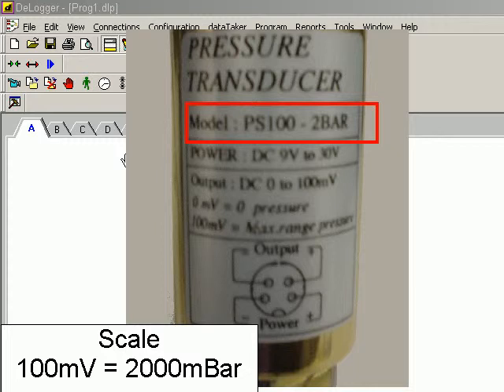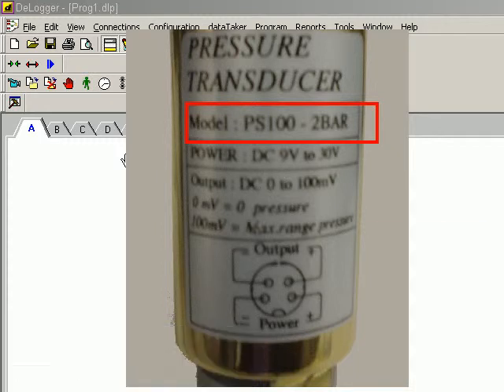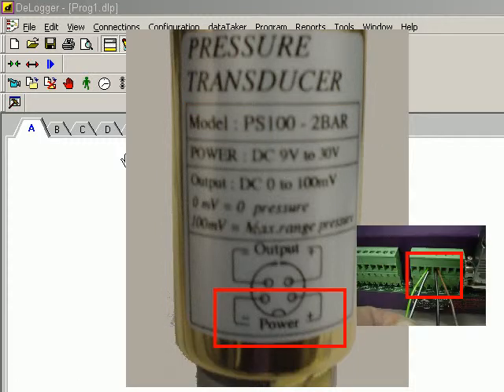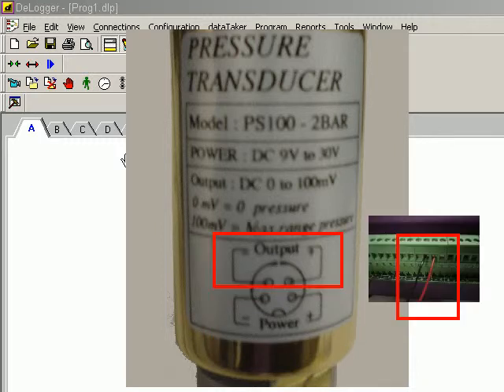The power plus and minus are connected to the power supply plus and minus. You need to double-check to ensure you've got the correct polarity, and the output of the transducer are connected to the channel 3 plus or minus terminals.